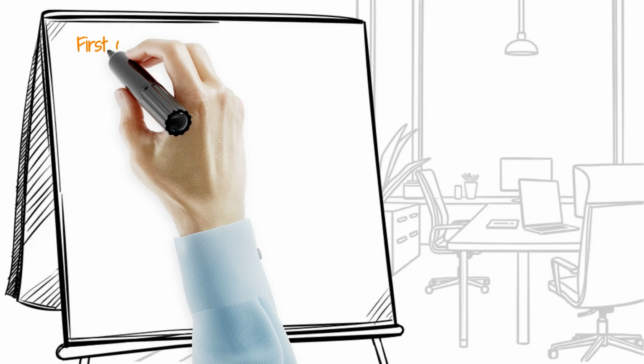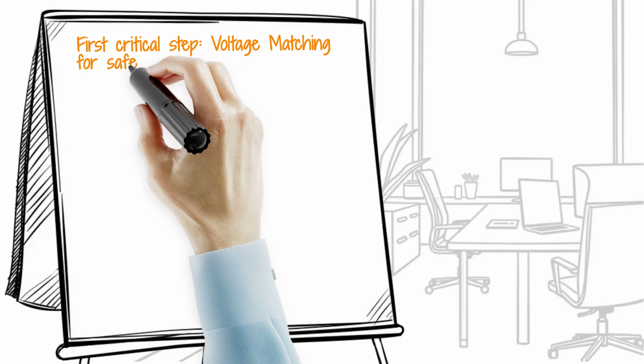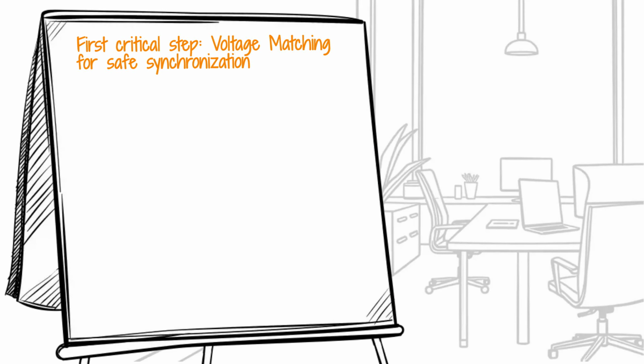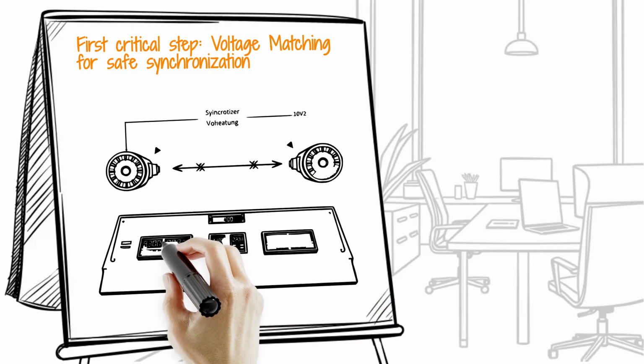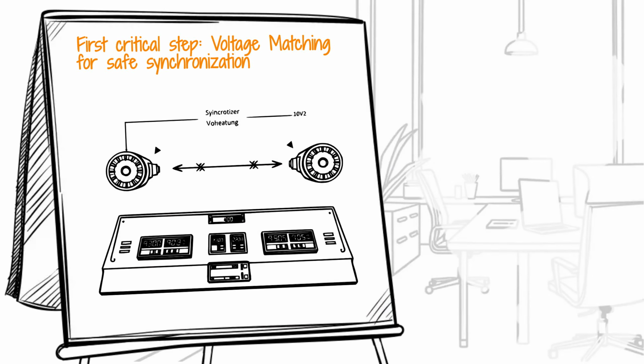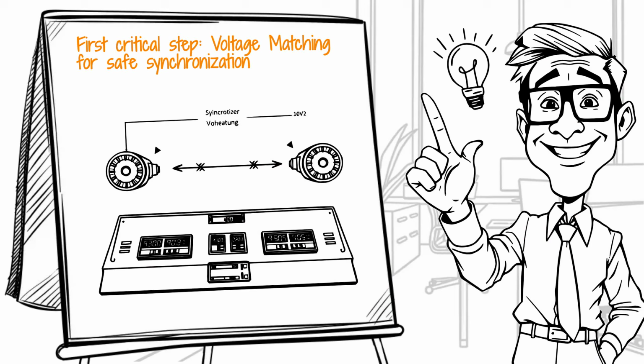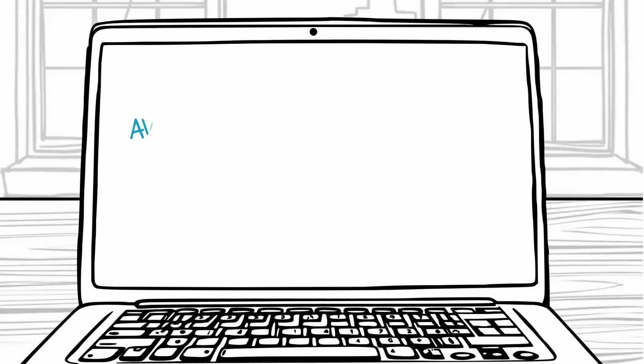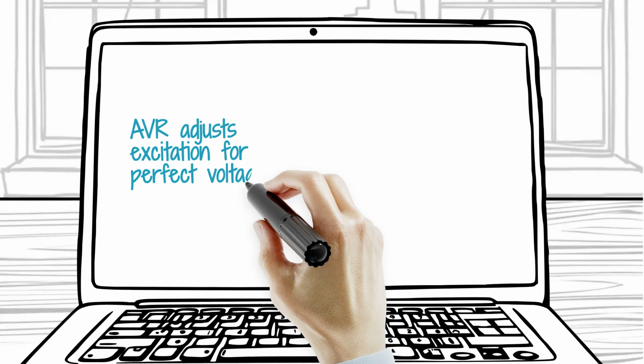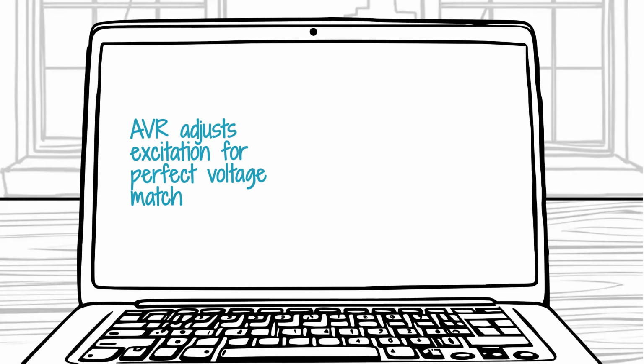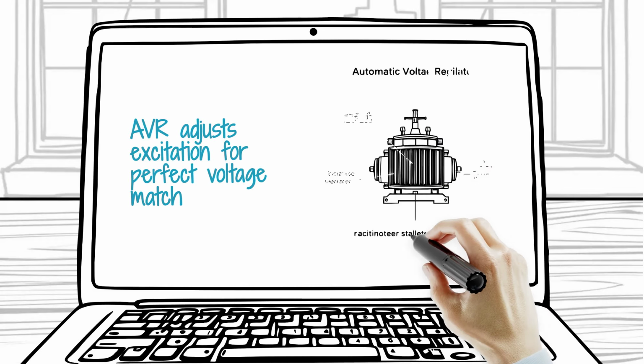First, voltage matching. The synchronizer continuously measures the voltage of the running busbar and the voltage of the incoming generator. It then sends precise automatic signals to the generator's automatic voltage regulator, or AVR. The AVR adjusts the excitation current to the generator's field windings until the incoming voltage is exactly equal to the busbar voltage. This step prevents the flow of unwanted reactive current once the breaker closes.